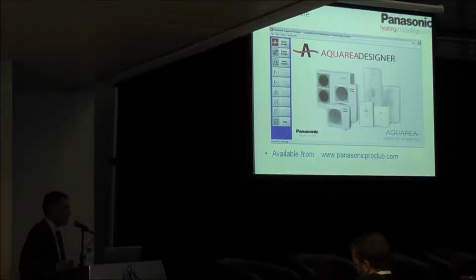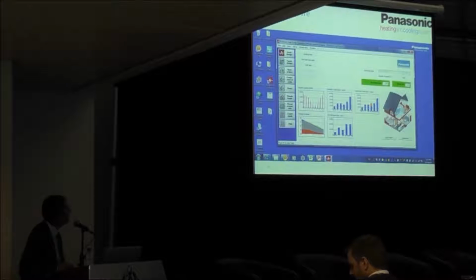Now there's software that we have on PanasonicProClub.com that has weather data already built in. You can either put in the size of the building and when it was built, etc., or you can put in your thermal load if it's been calculated by an engineer. What that will do is select a unit for you, whether it's a standard, high temperature, or TCAP. You can select which unit you want to go for, or the quantity of units. And it gives you a report.